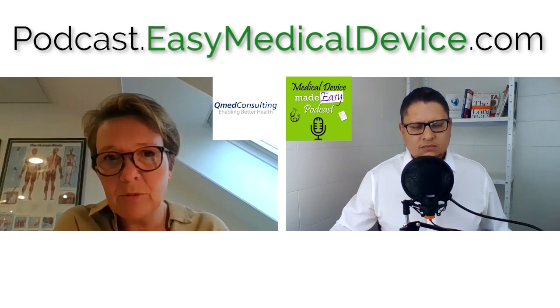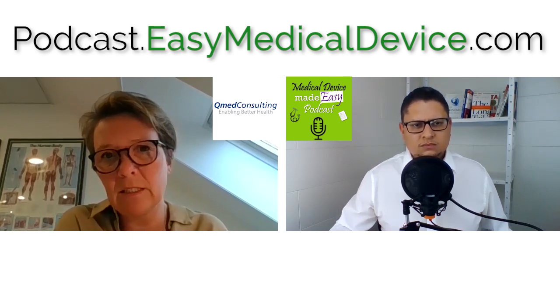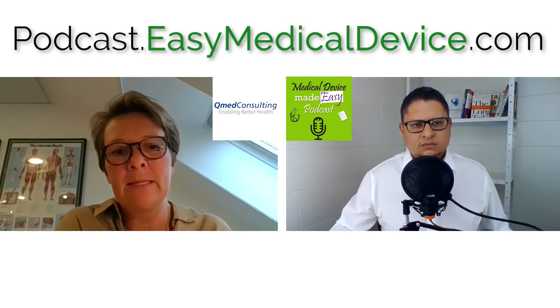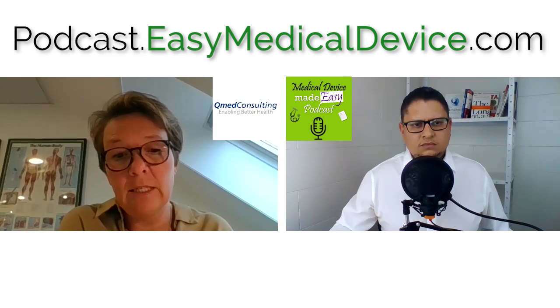But on the clinical evaluation report, we go in together with the client and do a gap assessment on where they want to be, which claims they want to use going into the market, and look also at whether, for legacy devices, there is sufficient data right now. It might be that some years ago we thought this would be okay and it was accepted by the notified body, but now with the new statements from the Commission and the notified bodies, this is no longer acceptable. So we will have to go back and set up a post-market clinical follow-up activity plan for them and write an updated clinical evaluation.